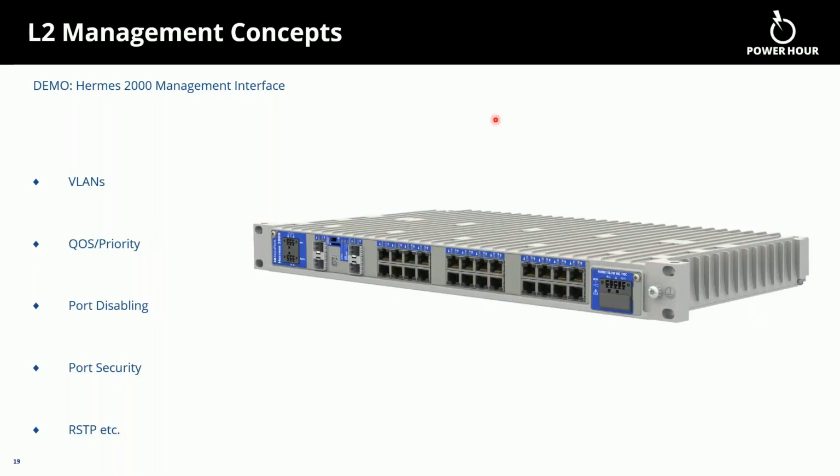There's also security things as well. You might be grouping by function, application, and then you also can even reduce congestion on your network. So one that I've heard in real life utility world is we have one switch, but we have cameras. And so they want to have the cameras and even their other stuff on the same switch because that's their constraint. But they don't want anything that would be on their, like a communication to their relays or something, to be affected by the cameras. So they're using VLANs for that.